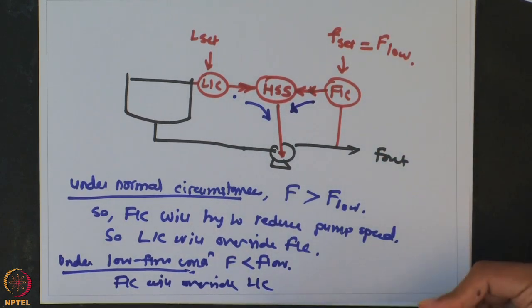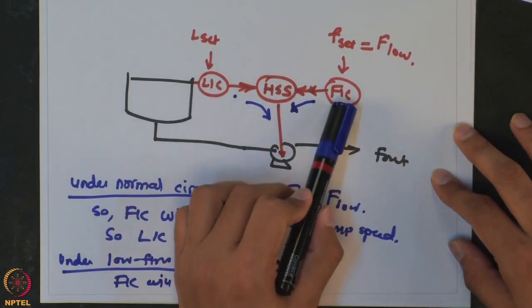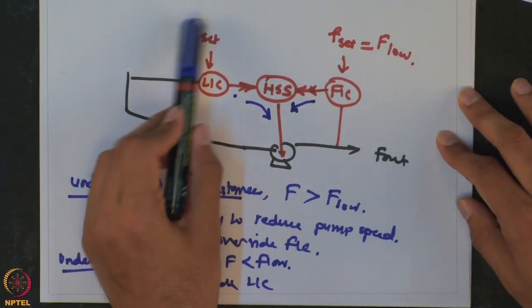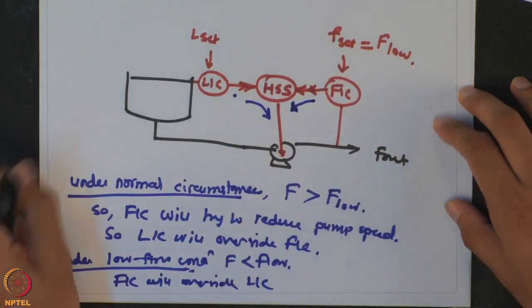By using the high selector switch, you can control both level and flow at or above their respective values. Level is the primary control variable and flow has a set point driven by safety conditions.